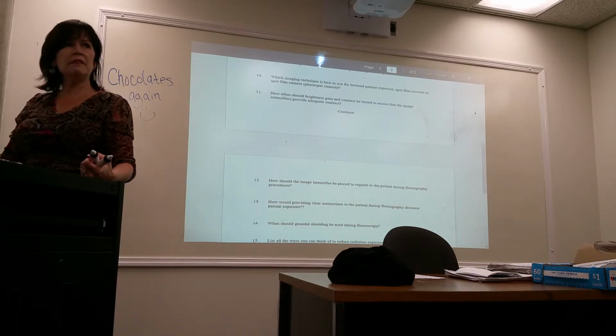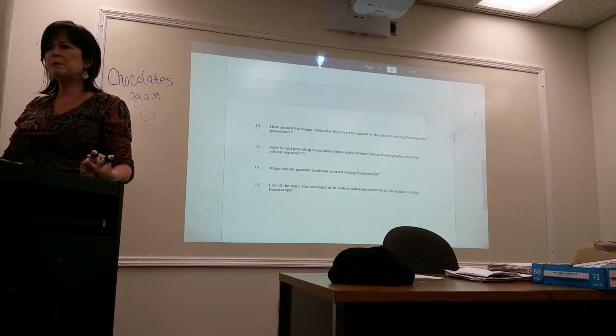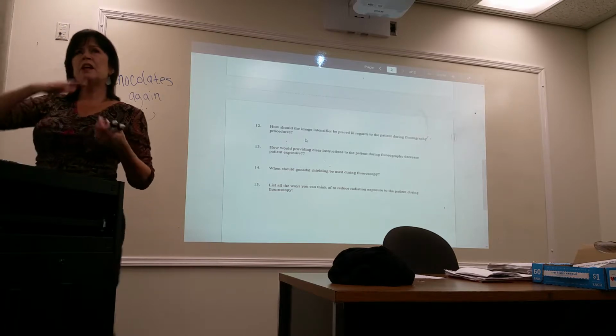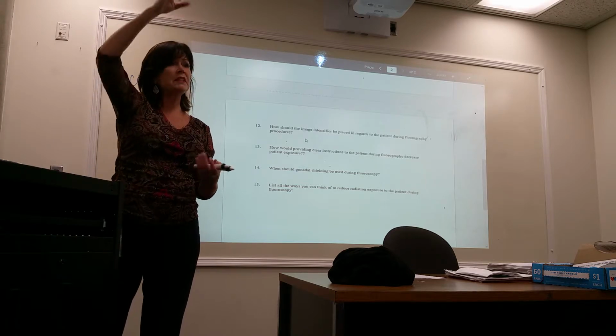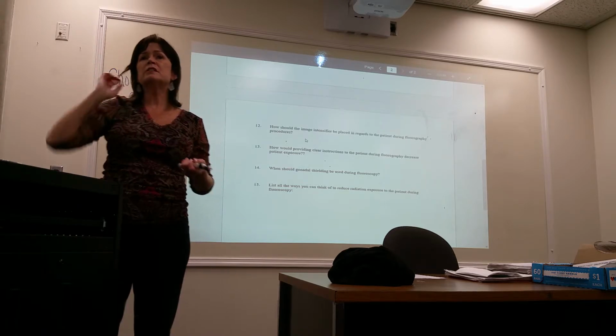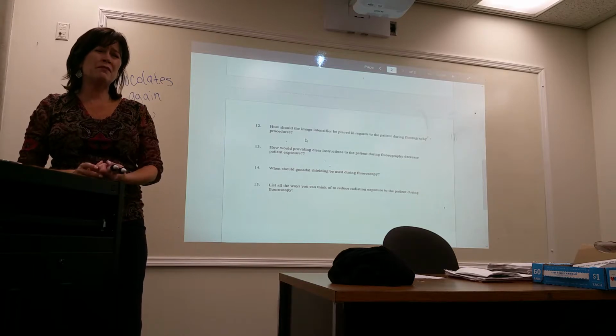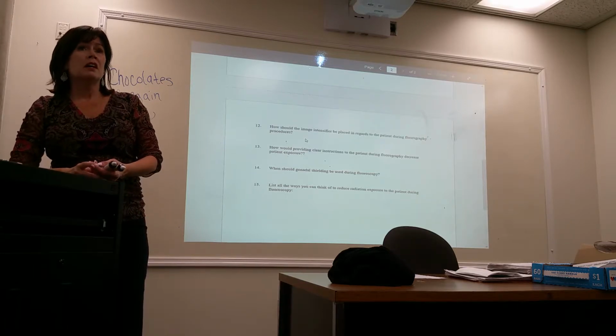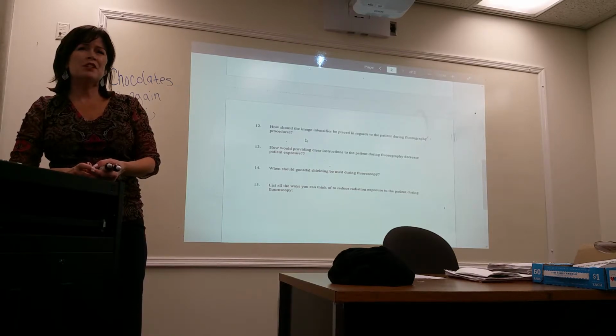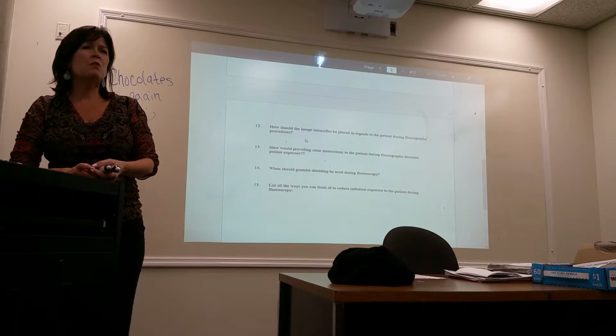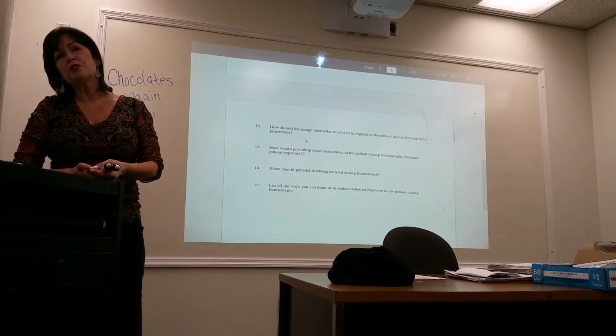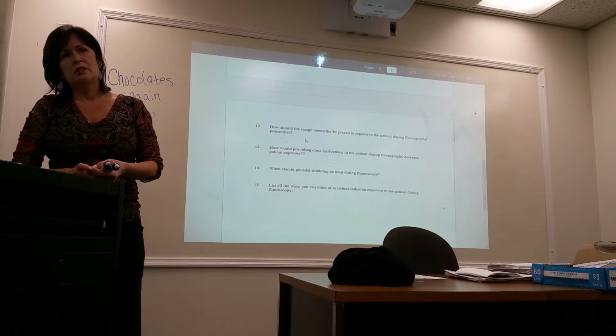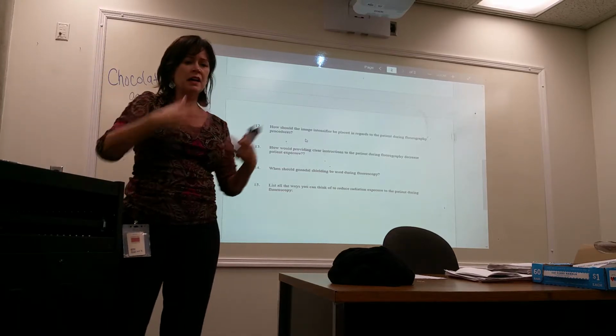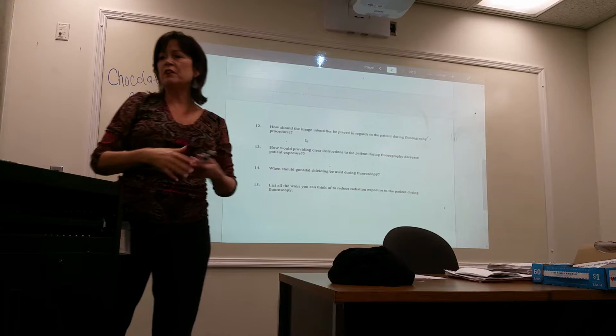And then number 12, how should the image intensifier be placed in regards to the patient during fluoroscopy? So, in other words, like, the II tube can move up and down, right? And so, is it better to be closer to the patient or away from the patient? Closer. Farther. Closer. Okay, what is the II tube? That is your image receptor. So do we want our image receptor further or closer away? Closer. So it's good to keep the image intensifier closer to the patient.